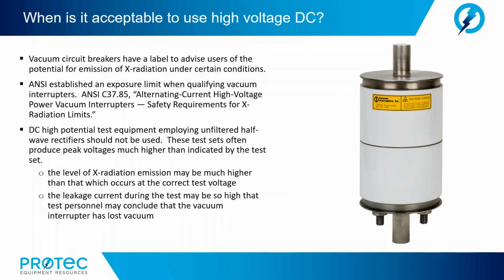Now, under certain conditions, a DC high potential test may cause a good interrupter to appear bad. For example, when a DC test voltage is used, a high field emission current from a microscopic sharp spot on one contact of the interrupter can be misinterpreted as a sign of a vacuum interrupter filled with air. Now, to avoid a misinterpretation of the test results with the DC, if a vacuum interrupter appears to fail the DC high potential test, retest the open interrupter at the opposite polarity.